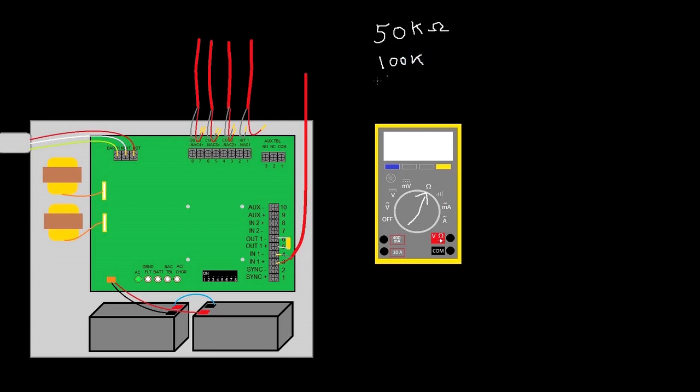Now those numbers though are not on individual circuits. So let's say your threshold was 100K. If you had 200K on this one and 200K on that one, because of those resistances in parallel, that's probably going to be flirting with the threshold.